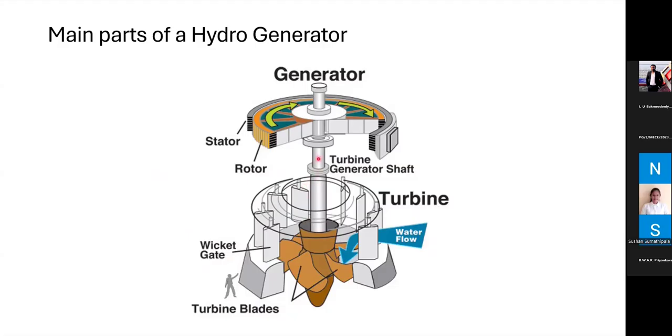The turbine and the generator shafts are coupled at the middle, and at the top you have the generator. Always the generator is at the top because the water has to go from the bottom to the tailrace towards the outflow of the power station. Due to the movement of the turbine at the same speed, the generator is rotated. There is no gearbox between the two shafts.